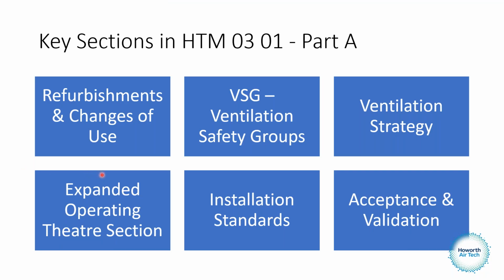So the key areas again going through, so we've got refurbishments and changes of use. Where previously some people may have taken a broom cupboard and turned it into a treatment room, we can't do that now, and this guidance is much clearer in tables like table 2. The ventilation safety group should manage every single aspect of the critical ventilation system, and that should tie in with the ventilation strategy, which is obviously tied again directly to net zero and reducing consumption and making our hospitals more efficient.